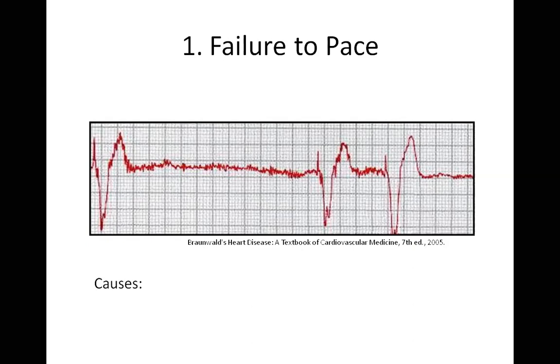Remember, we explained that the reason you use that mode is that when a patient is going to theater, a diathermy machine can be used. The diathermy machine acts like depolarization, electrical activity, and the pacemaker lead will sense the diathermy machine, thinking it is the heart generating intrinsic activity. And so it will inhibit pacing. Are you getting me, man? Yes, Chief. In that situation, the patient can go flatline on the machine, because the pacemaker thinks electrical activity is going on, not knowing that it is sensing the diathermy machine.